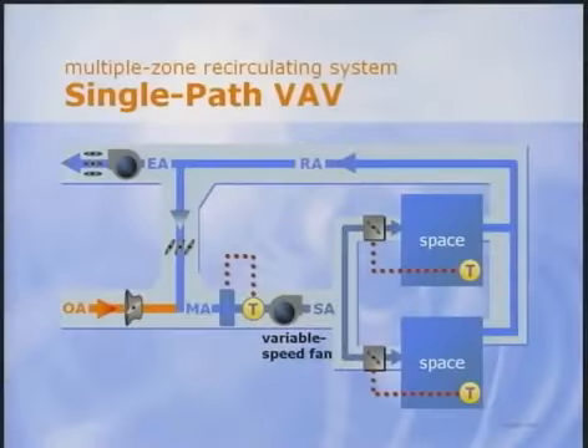Finally, let's look at a multiple zone VAV system. It consists of a central air handler or rooftop unit delivering primary air to many VAV terminal units. For each zone, the thermostat modulates primary air volume to match the cooling load in the zone.